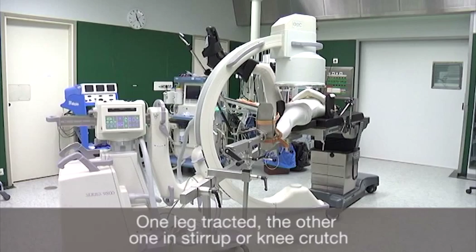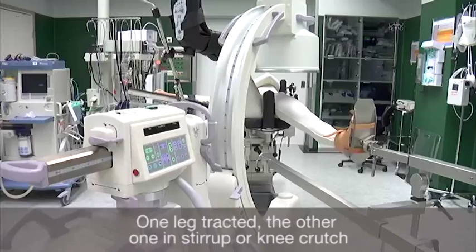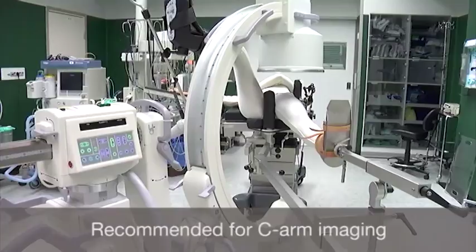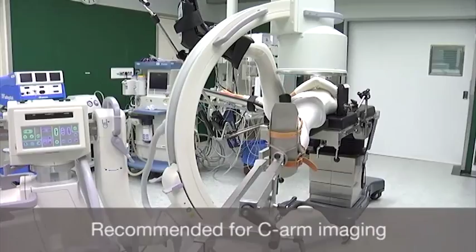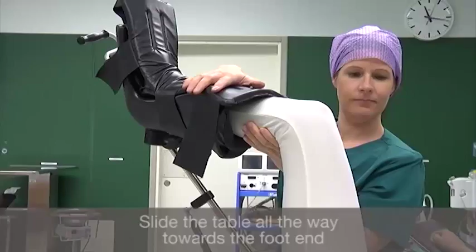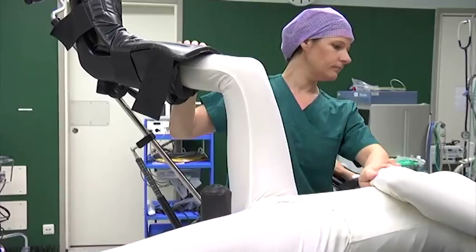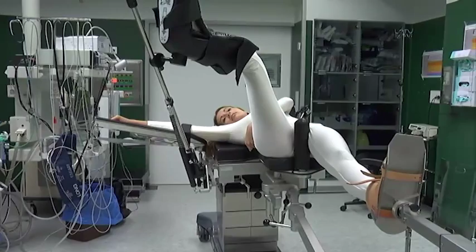For C-arm imaging, we recommend using a position where the other leg is lifted aside, either with a stirrup or a knee crutch. This position allows better access of the C-arm. It is also better for anatomical reasons, especially during C-arm use. Slide the table. Do the setup of the device as instructed in the manual. Here we have used a stirrup for the other leg.